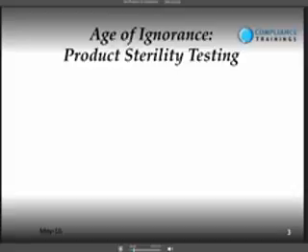But the test gives a warm, fuzzy feeling to management and the FDA, and believe it or not, final testing is still required for many drug products. The conclusion is that post-sterile testing has no practical quality assurance value for monitoring sterilization. It only detects gross process failures, again greater than 3% contaminated half the time. And the problem with most testing programs is you're never sure that you tested the worst case. It tells you you can sterilize something, not that you did, or if they are all sterile. This is why today post-testing is only used during validation or audits.